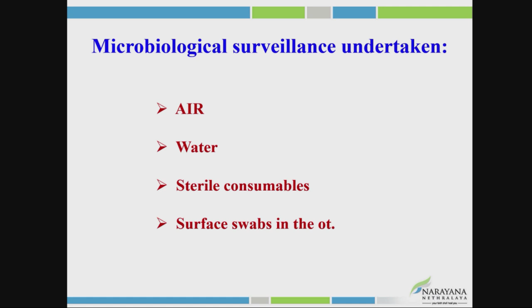To check the air, whether it is plenum air conditioning, laminar flow, or wall mounted, first you need to check the air quality using either a settle plate or air sampling. The settle plate should cover the entire area of the OT - entry of the OT, both corners, and backside of the OT, both corners and center. Or if you have the facility of air sampling, you can do air sampling by measuring the area or size of the OT.